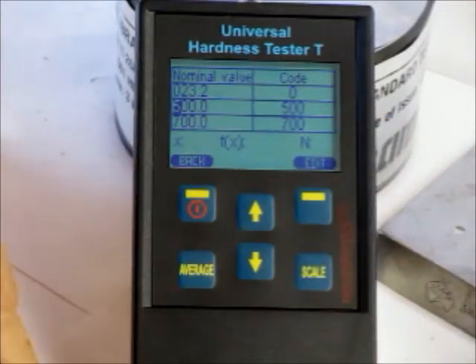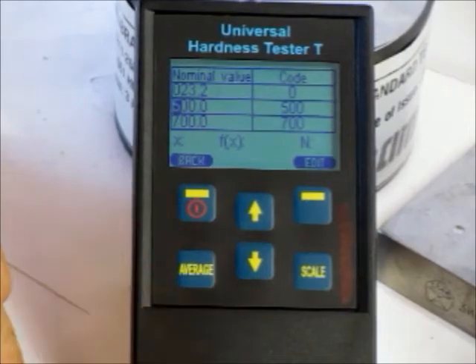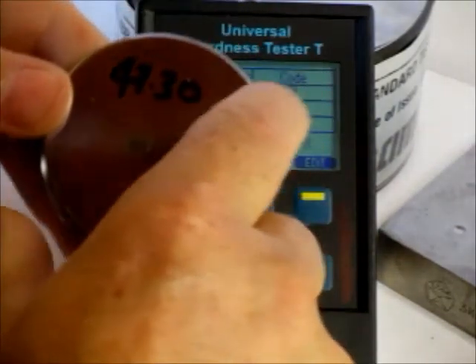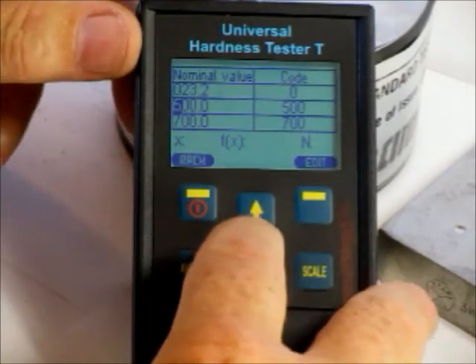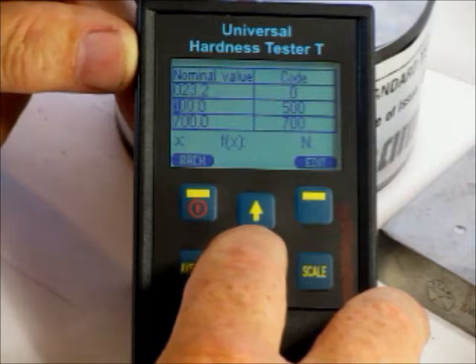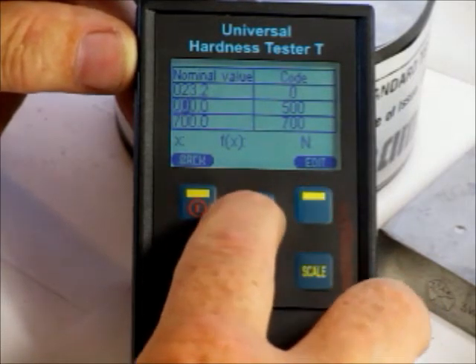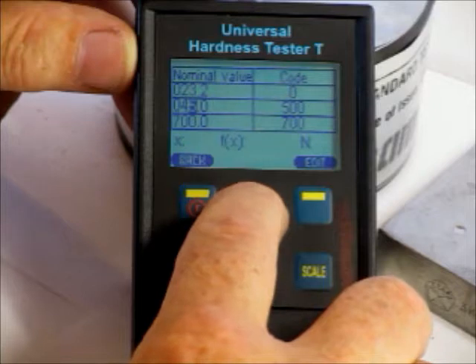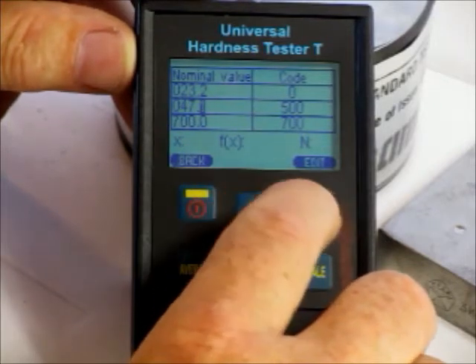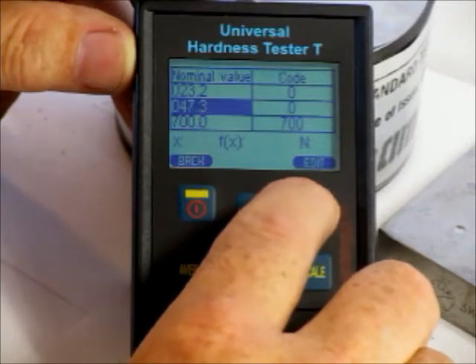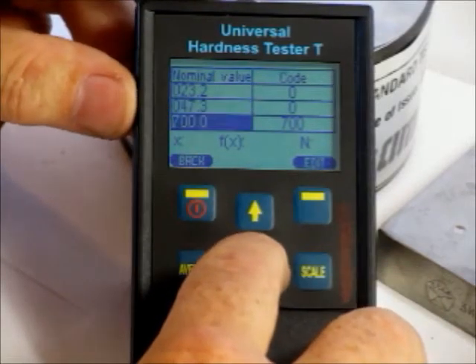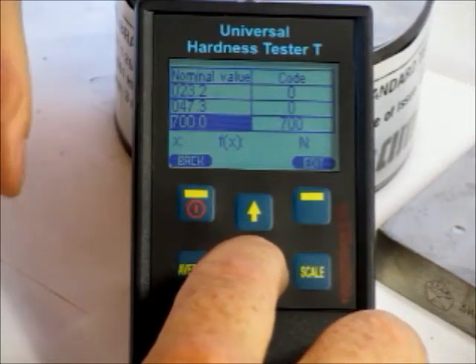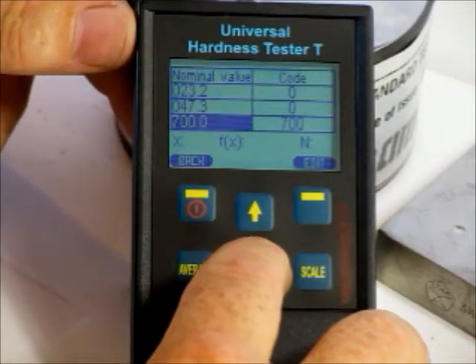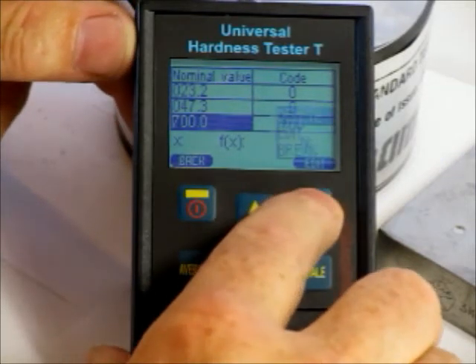and what I want to do here is my second test block in my range is 47.30, and so here 47.30, I'm now going to change my values for this to be 47.30, so here we go to 0, edit, up to 47, edit, edit, and then we're just going to put in the value of 3. It goes background onto the third one, which is we do 3 in the range, make sure we're covering the whole range for our hardness testing for this particular material of alloy steel. I hit the edit button, and I put in the value of this one.